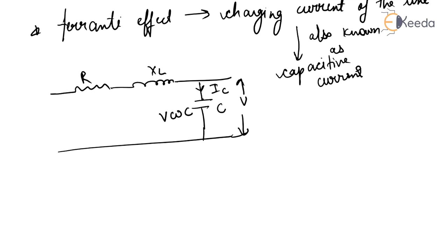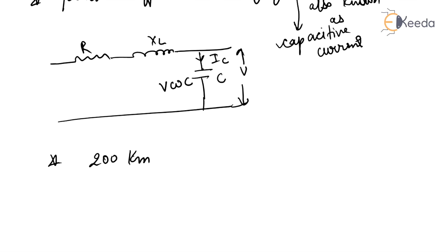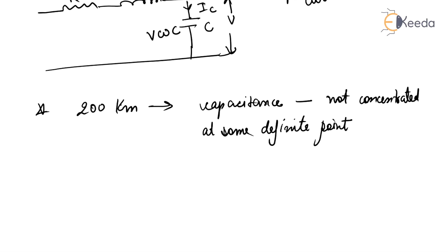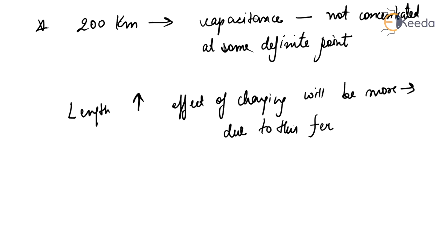The Ferranti Effect occurs because capacitance and inductance are the main parameters of the line, for lines of 200 km and above. The capacitance is not concentrated at a single definite point; it is distributed uniformly along the whole length. When capacitors are connected in parallel, the total capacitance C equals the capacitance per unit length times the total length. As the length increases, the effect of charging current becomes greater.